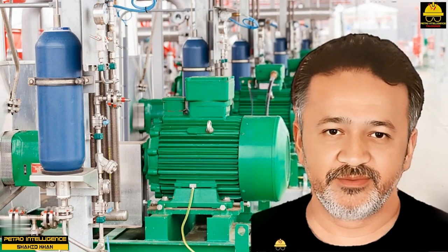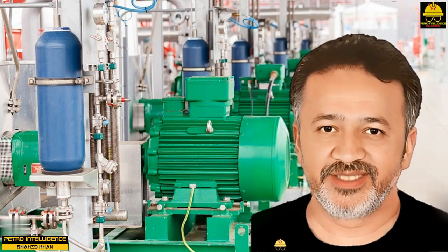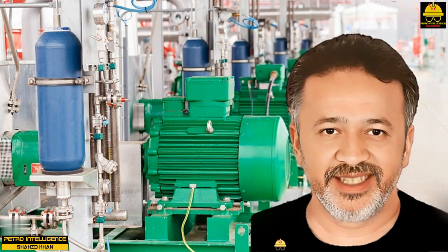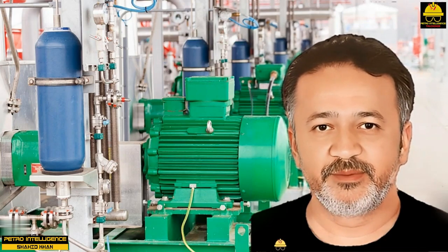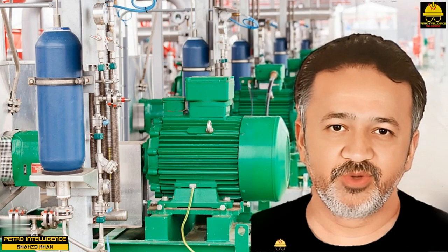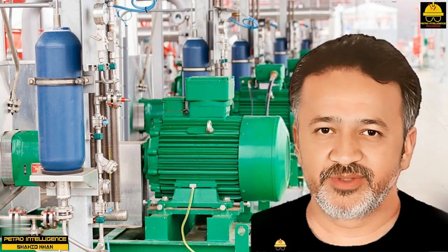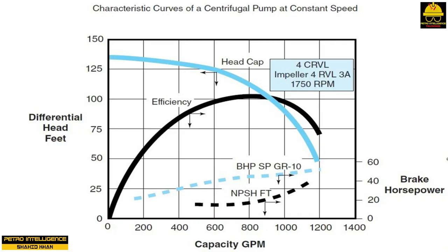Pump curves. Centrifugal pumps are designed to work in specific services at specific rates. The best operating condition for a pump usually is indicated on the pump's efficiency curve. The efficiency curve includes several values: flow rate in GPM, total head in feet (discharge head minus suction head, sometimes called differential head), pump efficiency, required pump horsepower, and pump NPSH.